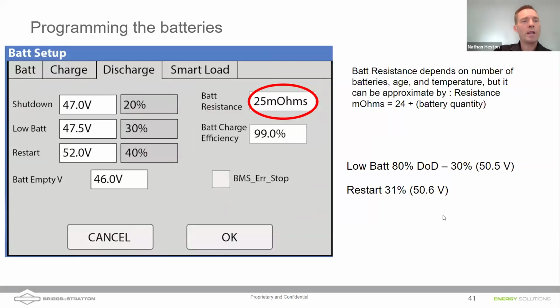Another important thing to set up is when you get into the discharge settings of the battery, that top tab, you'll want to set that battery resistance. If you're typically discharging these batteries in cold environments, you might want to use a slightly larger resistance. For our batteries, they are about 24 milliohms divided by the number of batteries you have, because if you have batteries in parallel, the overall resistance of the bank is less than the resistance of an individual battery. So you can set this here. You'll also want to set this battery empty percentage. It'll make the inverter shut down before the batteries do, to prevent over-discharging those batteries and having that hard stop when the batteries go through a shutdown.